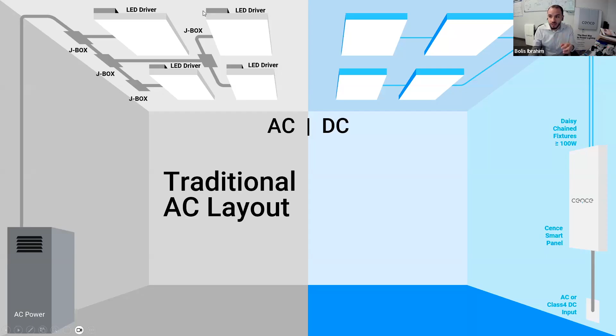This lends itself to another benefit for DC: centralized DC drivers versus decentralized AC drivers. You have the benefit of removing the driver from the fixture or device, removing the point of load converter. Instead of it being on the device in maybe an inaccessible location, you can move all of these into a centralized cabinet and do direct current distribution to your DC loads.